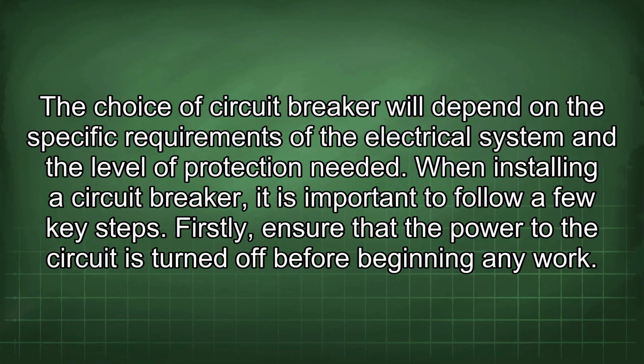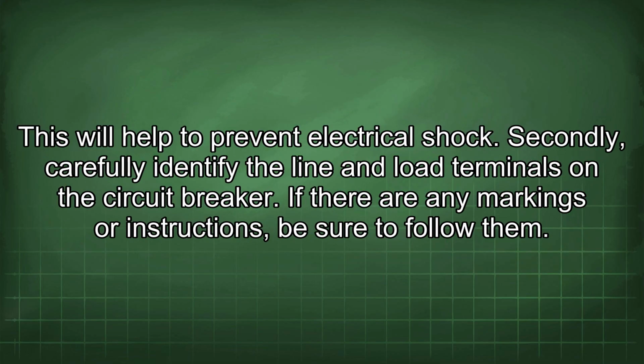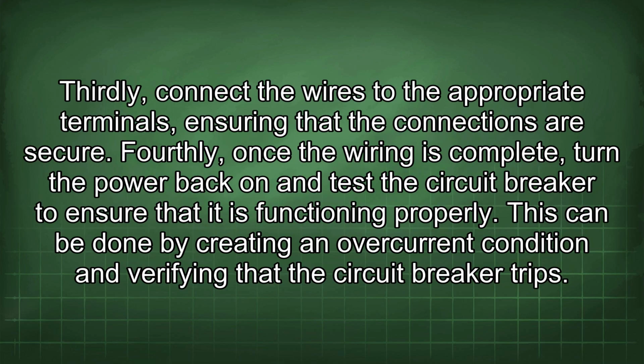When installing a circuit breaker, it is important to follow a few key steps. Firstly, ensure that the power to the circuit is turned off before beginning any work. This will help to prevent electrical shock. Secondly, carefully identify the line and load terminals on the circuit breaker. If there are any markings or instructions, be sure to follow them. Thirdly, connect the wires to the appropriate terminals, ensuring that the connections are secure. Fourthly, once the wiring is complete, turn the power back on and test the circuit breaker to ensure that it is functioning properly. This can be done by creating an overcurrent condition and verifying that the circuit breaker trips.